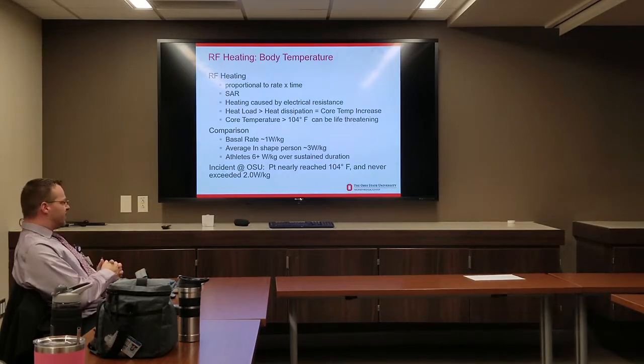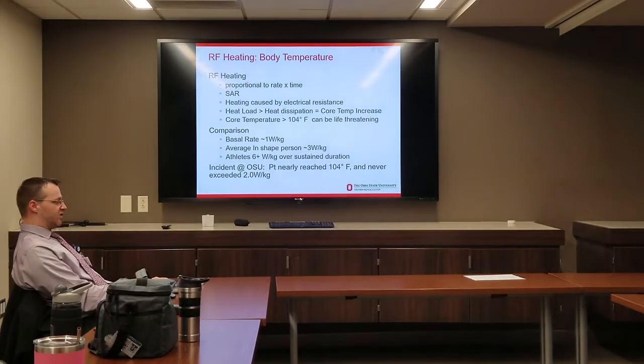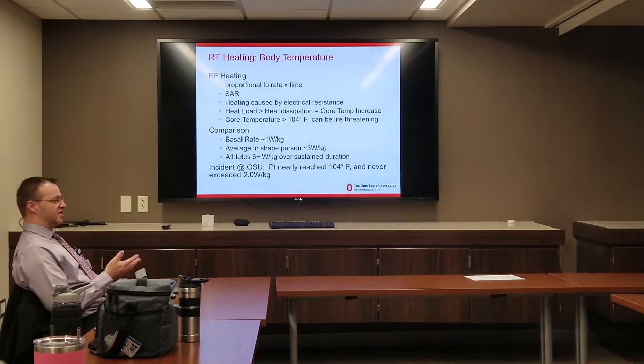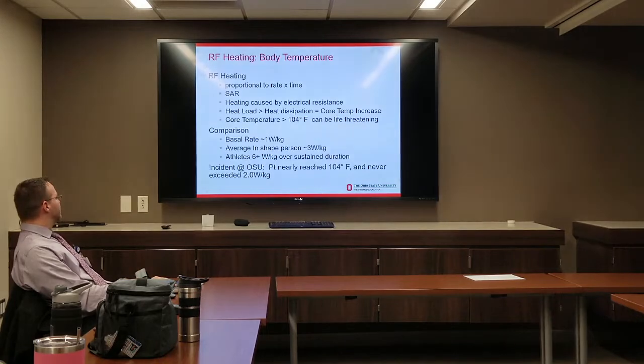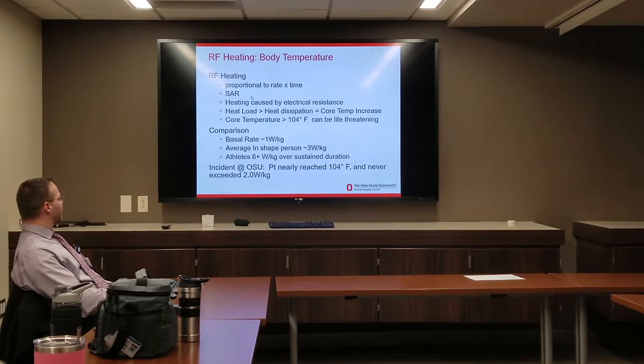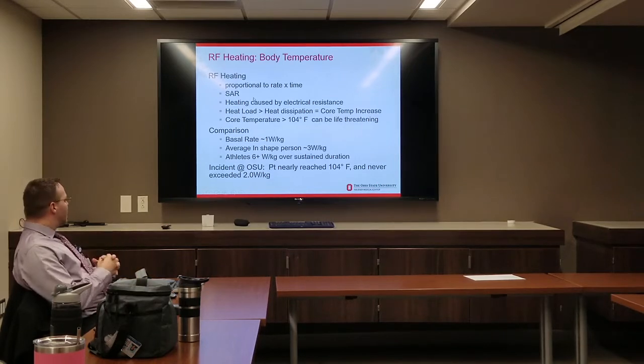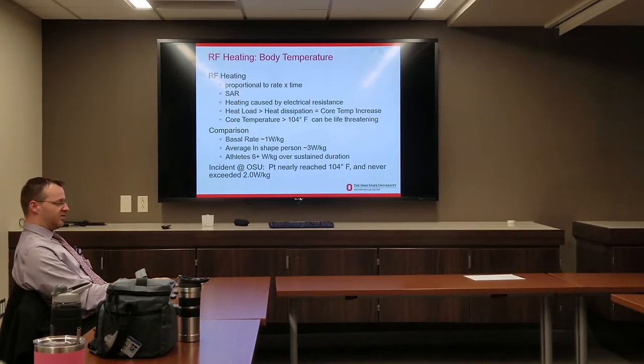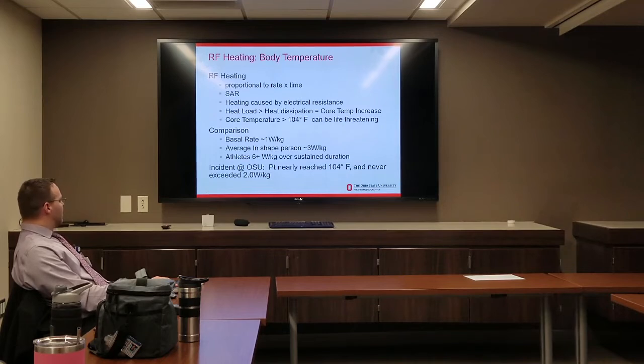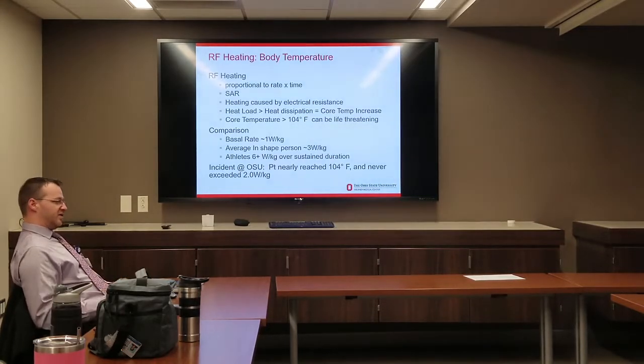For RF heating in regards to body temperature: RF heating is proportional to the rate and time that RF is applied. More RF deposition over a longer period results in more body heating — this is what SAR measures. The heating is caused by electrical resistance in the body. If the heat load is greater than the patient's heat dissipation rate, their body temperature will rise and they'll start getting uncomfortable and sweating. A core temperature of 104°F can actually be life-threatening. There are conditions where a patient's thermal regulation is reduced, and using a lot of RF power over a long period could increase body temperature to a dangerous level.